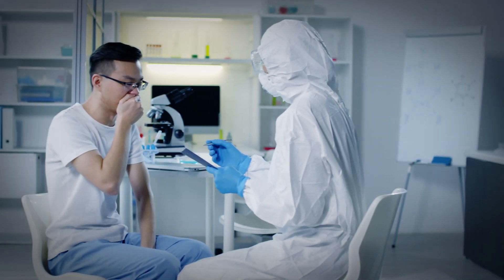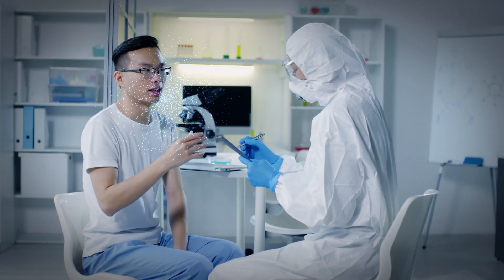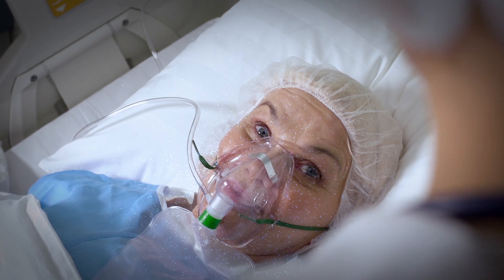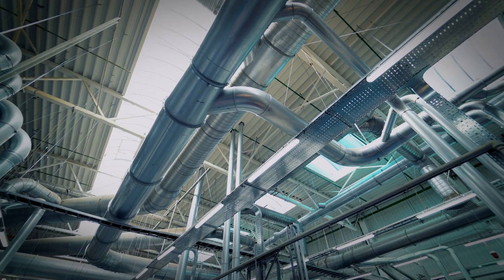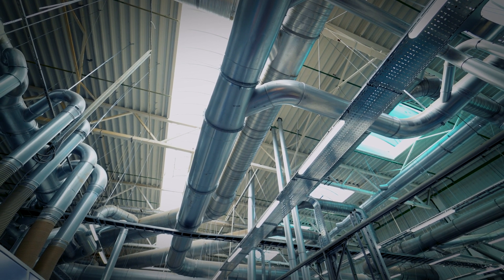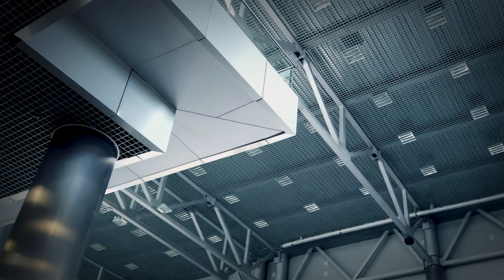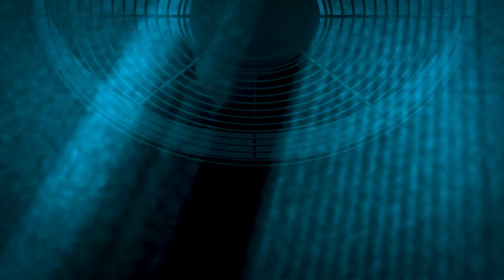Patients coughing or being ventilated will project droplets, some containing the virus as an aerosol. They are so small that they may take tens of minutes to fall to the floor as the droplet evaporates in still air. But if the space is already air conditioned, such large halls tend to have a regular grid of air inlets alternating with exhausts at roof level. Top-down air conditioning creates turbulent flows which can mix and spread droplets containing the virus very widely.